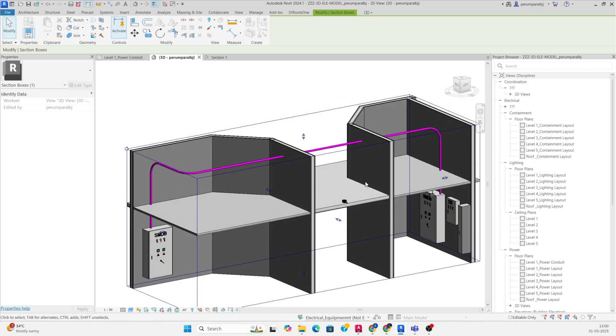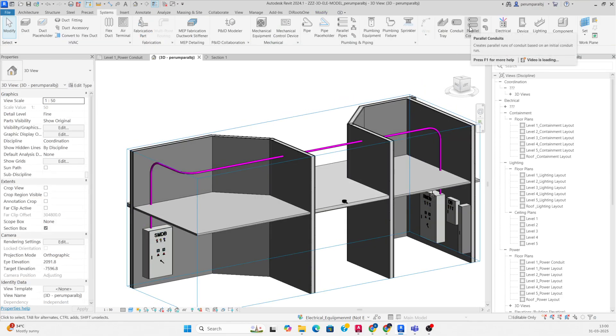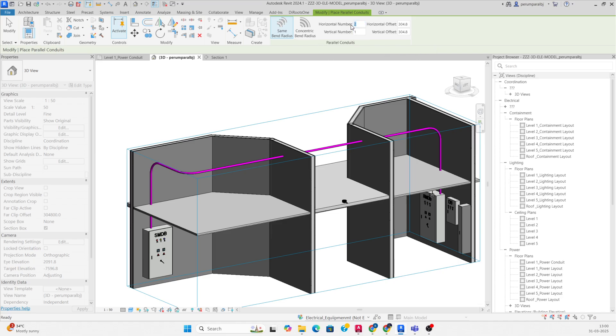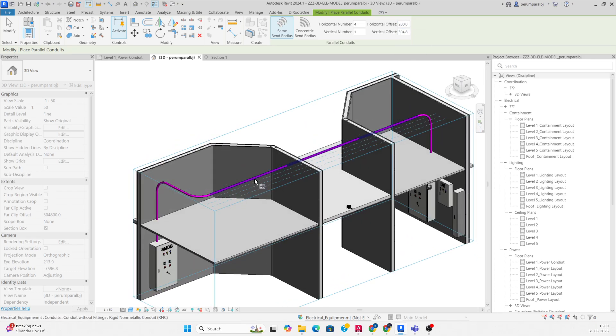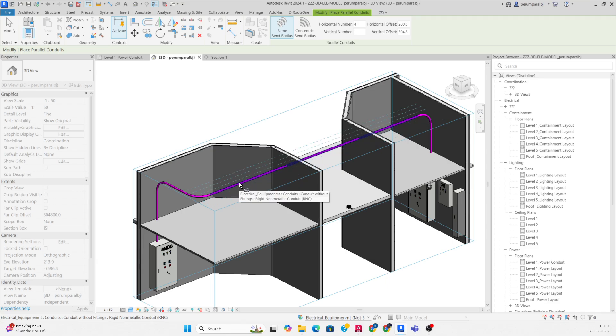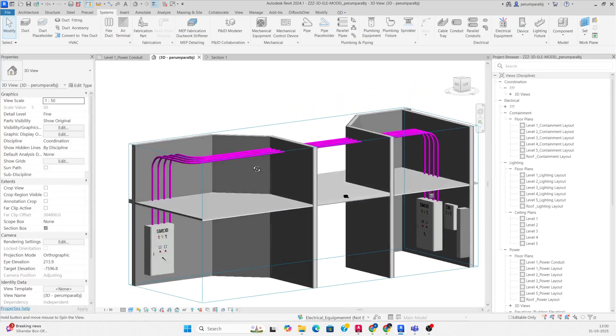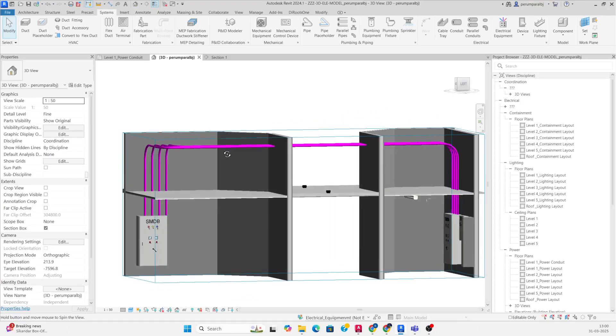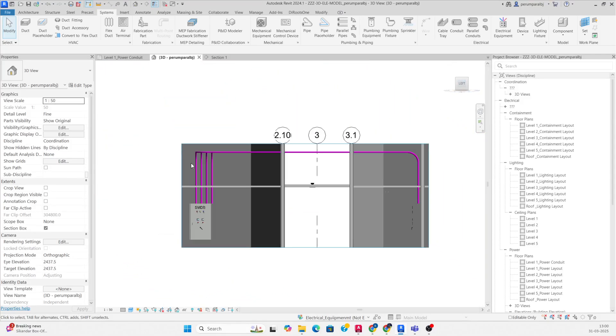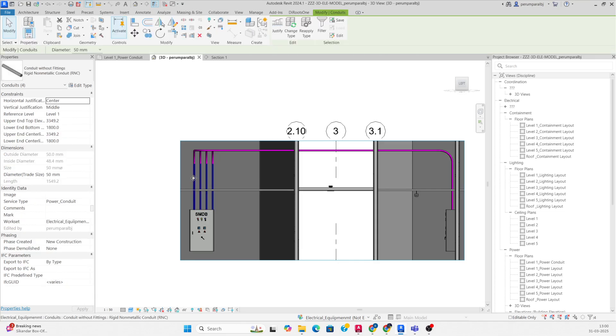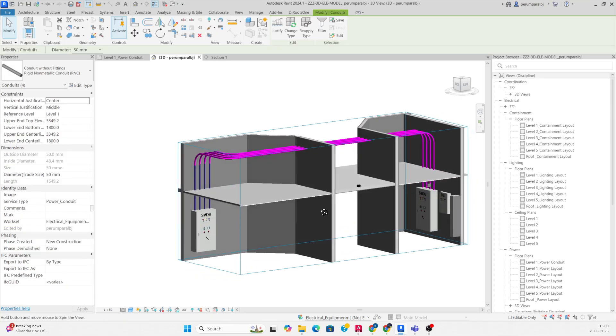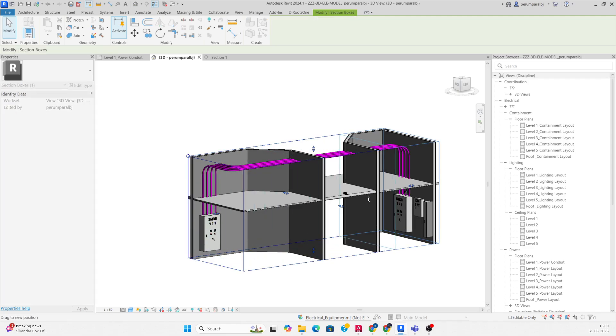For four parallel conduits for this panel, I need to drop this section. Select the parallel conduit tool, set four conduits with a gap of around 200. When you select, you can see it highlighting like that. Just tab to select — automatically those conduits are selected and created. You can then adjust them to the panel.